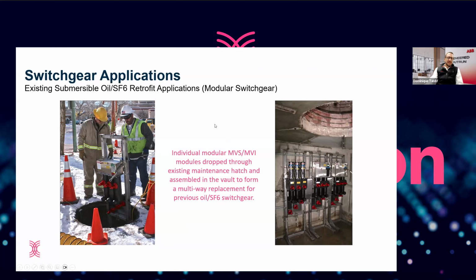The advent of the Elastimold elbow also led to developing dielectric switchgear. Because the elbow could hold back its dielectric and contain the electricity, we were able to start making very compact, dead front switchgear, just like the cable accessory products. This wasn't one of the newest designs, but the modularity, or pack-out modularity, let us put the system into a frame that can be lowered through an existing maintenance hatch.